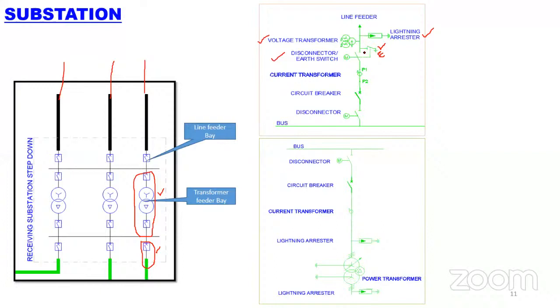What is the reason for it? Before that, you need to understand why we are putting the earth switch on the line. Basically, the earth switch is a protective device. When your transmission line is connected to the other end of the station, let's say a generating station, power is traveling from the generating station to the receiving station. Say I'm switching off the particular feeder, it means the generating station side, I'm closing the transmission line for maintenance purposes. Then we need to open this isolator and close this earth switch, because this is for safety reasons, in case someone switches on wrongly, so that electrocution should not happen. So for safety reasons, this earth switch is placed. Normally, when this feeder is in switched off condition, the earth switch will be in closed position.